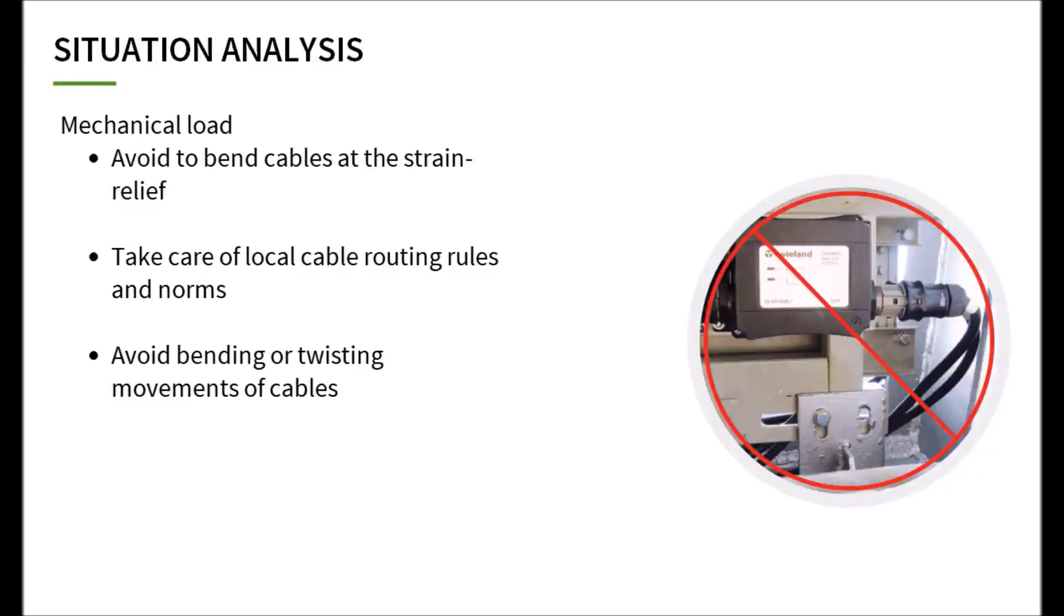Mechanical Load. Avoid kinking the cables in the strain relief area. The applicable guidelines for laying cables must be observed. Tensile forces on the contact points of rigid conductors larger than 2.5 mm² are avoided by first bending the cable and then further processing it. Mechanical bending movements in the strain relief area must be absorbed by suitable measures, e.g. cable clamps.